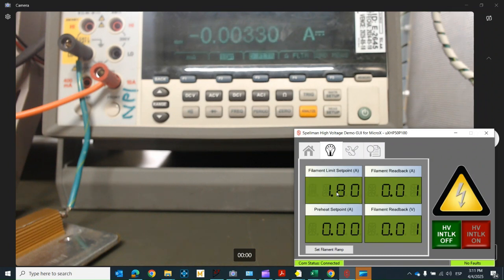We will now proceed to program filament preheat and filament limit values. Filament limit will be programmed to 1.8 amps and filament preheat will be set to 1 amp. You will notice that since the interlock is turned off, the filament preheat control is dominating and only the preheat current is available.